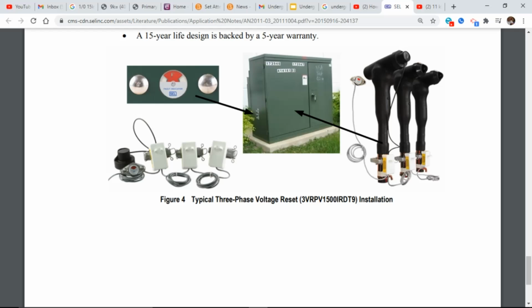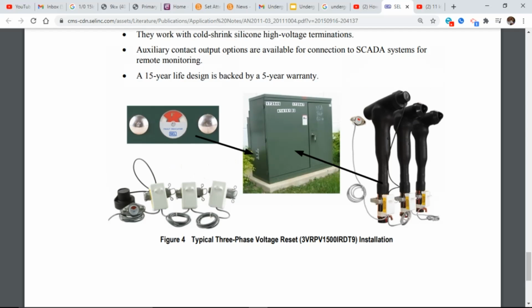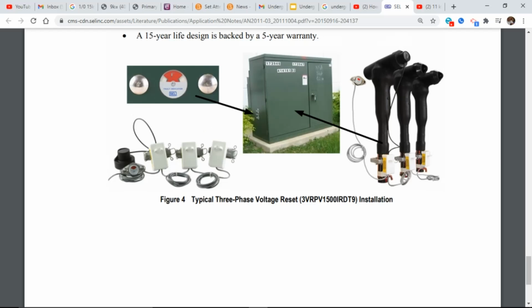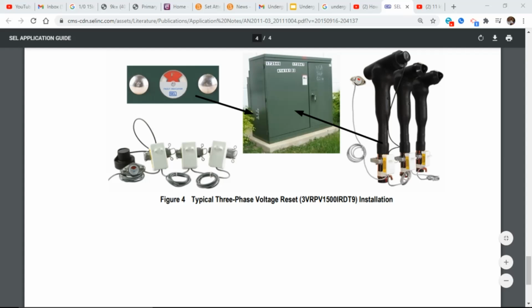So the indicator is not measuring current; current is an effect. The magnetic field is what's being measured. Essentially, all they have inside these things is an opposite magnet. They've got a north-south magnet sitting in this thing, and once the magnetic field gets too high, it trips the indicator. No battery is required. Nothing's required in this. That's the nice thing about it. You don't have to replace anything because all I have in here is a magnet. So these things can be sitting on the cable forever.